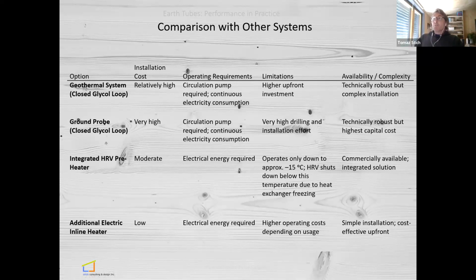Instead of an earth tube, other systems would be a geothermal closed glycol loop or ground probe, with an integrated HRV preheater, which operates until minus 15 degrees Celsius. After that, it shuts down, or the heat exchanger freezes. Or you install an additional electric inline heater before the incoming air goes into the HRV or ERV. Each of those has an installation cost, which can be relatively high. The additional electric inline heater is pretty low, but there's always energy required, right?